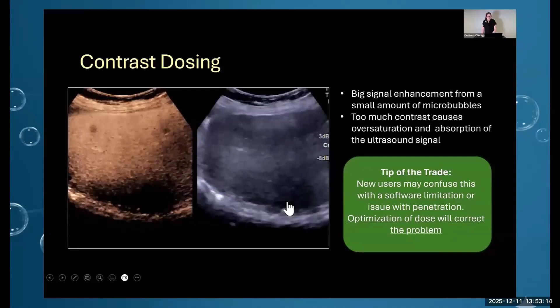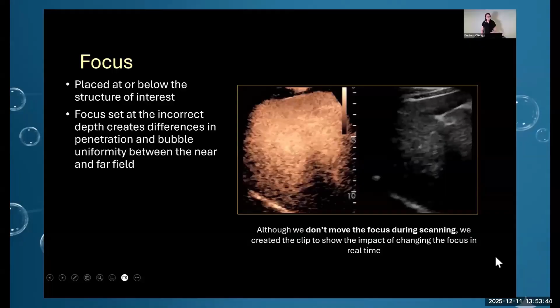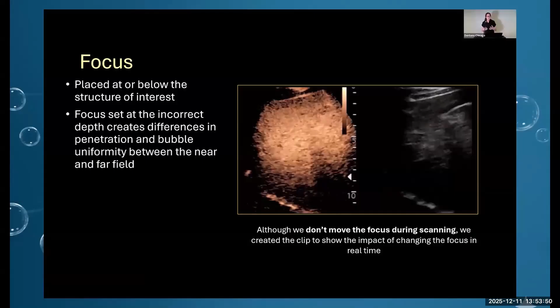So although we don't move the focus during scanning, we created this clip to show the impact of changing the focus in real time. You can see as the focus moves up, you completely lose the image in the background liver. And as it moves down, you have better bubble distribution from the near field to the far field. So let's put these together and look at a case of liver and kidney imaging.